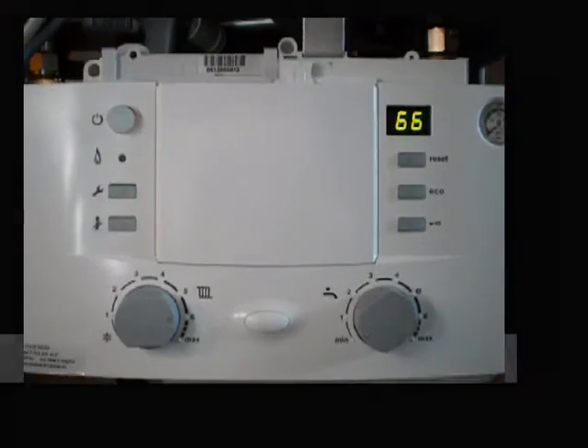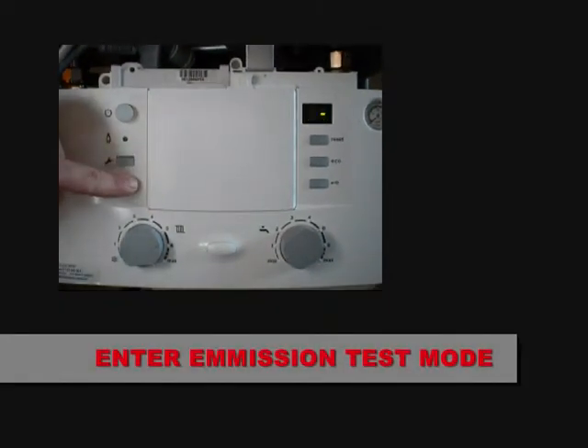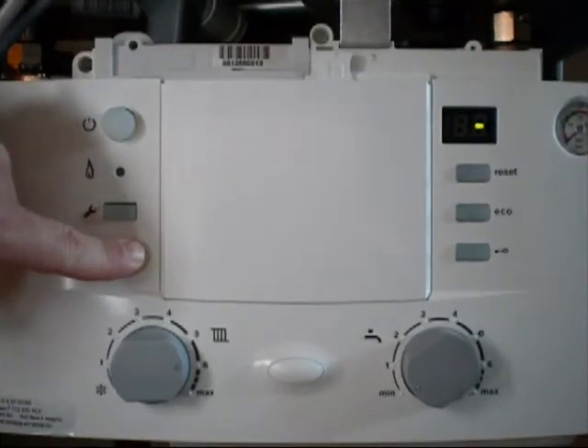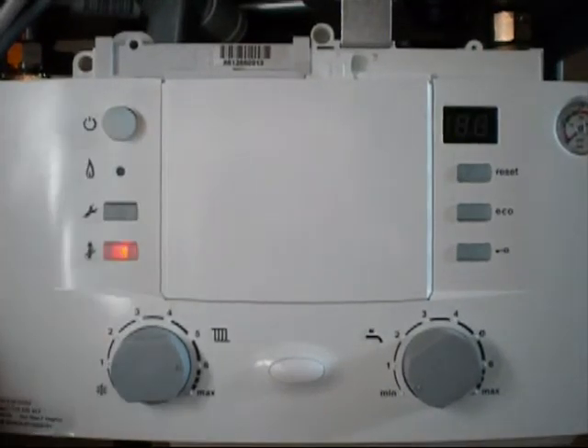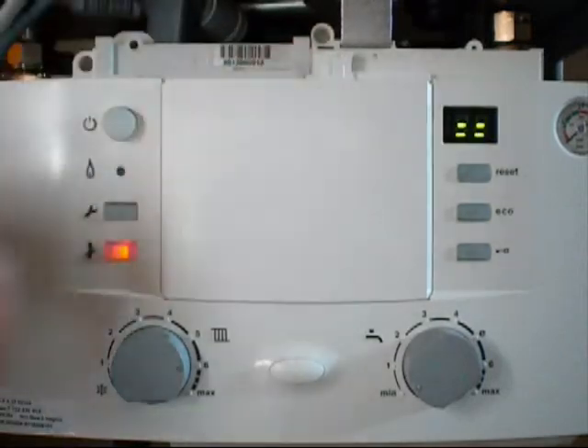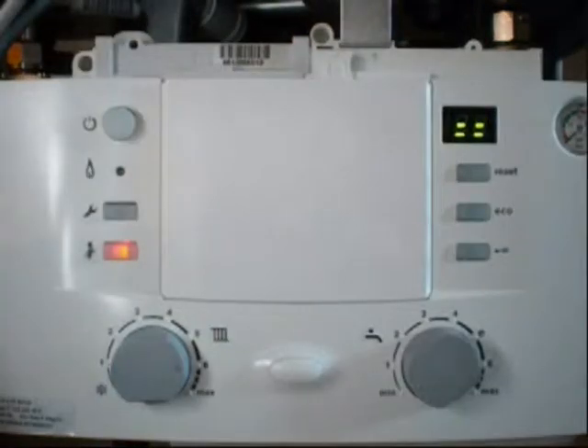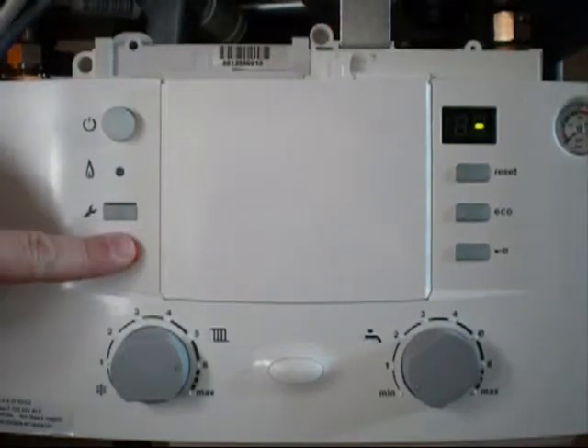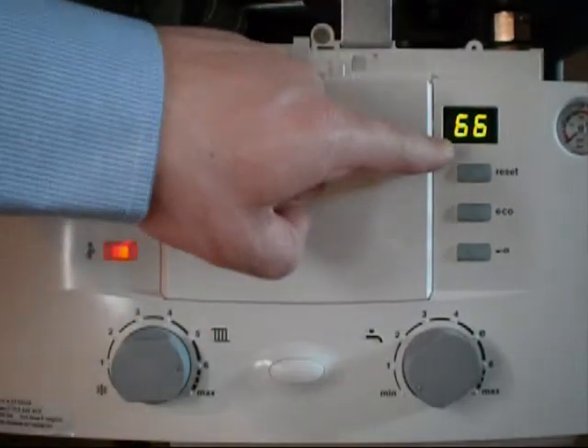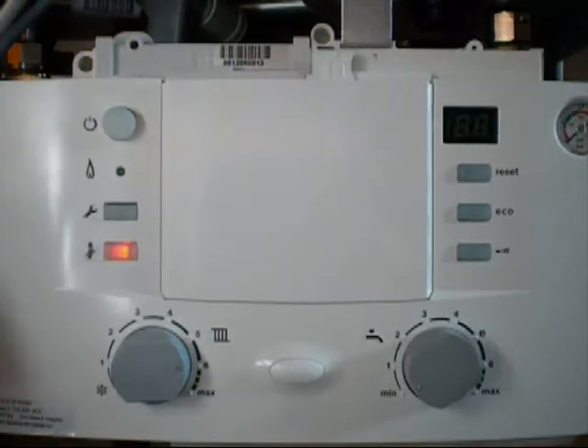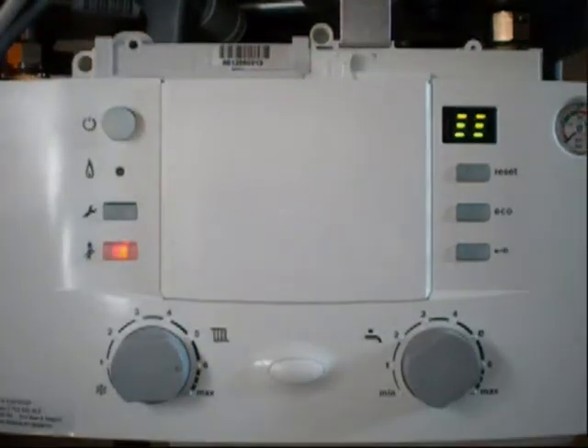Perform a flue gas test. Enter the emission test mode by holding in the chimney sweep button until the temperature and 4 bars alternate on the display. 4 bars indicate that the burner is firing at the maximum output set point on the dial. Press the chimney sweep button again. The temperature and 6 bars will alternate on the display. 6 bars indicate that the boiler is now firing at its high fire maximum nominal output. High fire combustion readings are taken at this point.